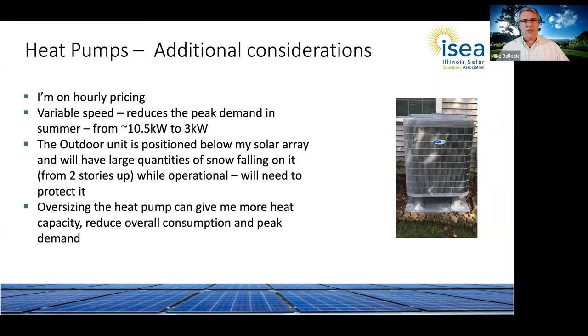The last one is also really important, and this is one that a lot of contractors may not be aware of or bring up themselves. I'll have a drawing later to show you more about this, but it's about oversizing the heat pump. A contractor might come in and say you need a 3-ton or 4-ton unit, and I might say give me the 5. I'll talk about why I did end up oversizing the heat pump. It can give me more heat capacity in winter when it's cold, reduce overall electricity consumption as well as peak demand, and it's going to reduce my gas usage too.